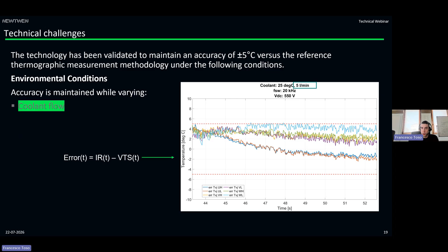What you can observe is that the model is capable of predicting this time-varying boundary condition and to adjust the thermal dynamic of the current, thanks to an inference model that is using the polydiodes inside the power module itself. So by the thermal response of the implemented sensor in the power module, the model is capable to understand that there is a time-varying boundary condition and to correct, by consequence, the junction temperature estimation and dynamics, holding a very good accuracy, 5 Celsius degree, an accuracy coherent with the measurement tolerance of an IR camera.